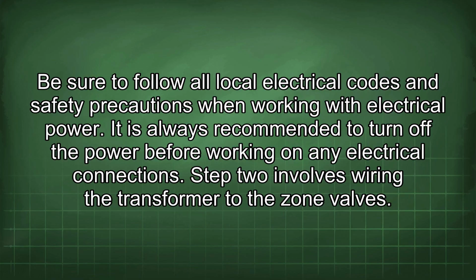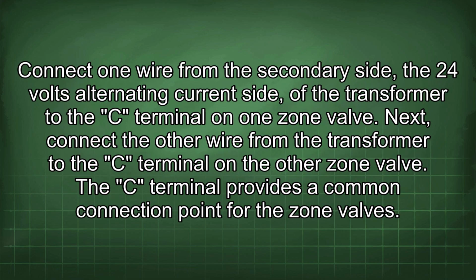Step 2 involves wiring the transformer to the zone valves. Connect one wire from the secondary side, the 24 volts alternating current side of the transformer, to the C terminal on one zone valve. Next, connect the other wire from the transformer to the C terminal on the other zone valve. The C terminal provides a common connection point for the zone valves.